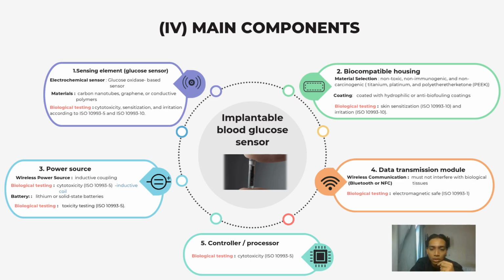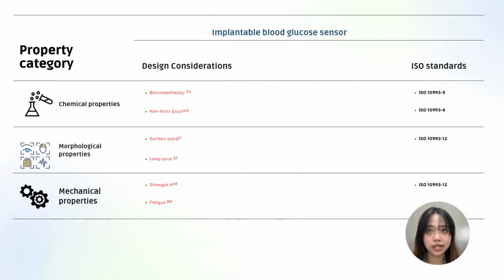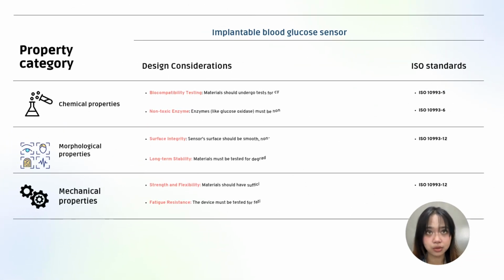And then the next component is the data transmission module. It usually uses wireless communication such as Bluetooth or NFC. This type of module must not interfere with biological tissues, so it must undergo biological testing of electromagnetic safety based on ISO 10993-1. And then the last component of the implantable blood glucose sensor is the controller or processor. This component must undergo biological testing of cytotoxicity according to ISO 10993-5.